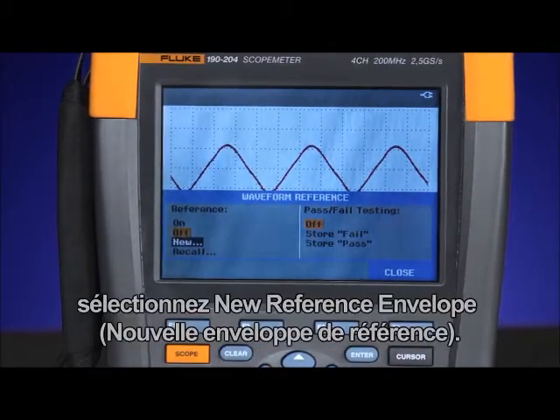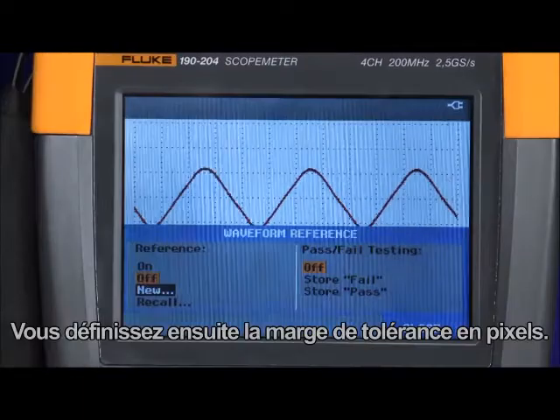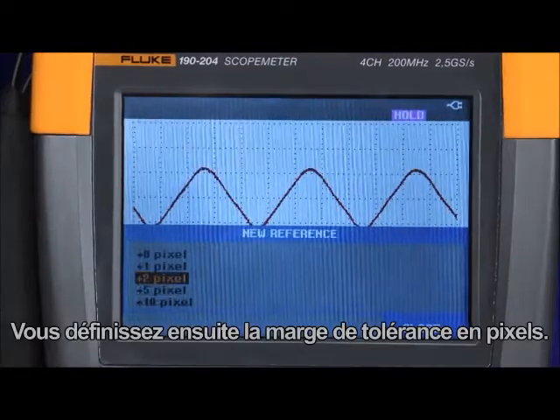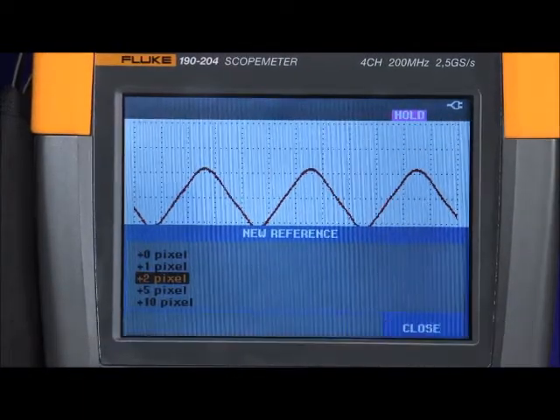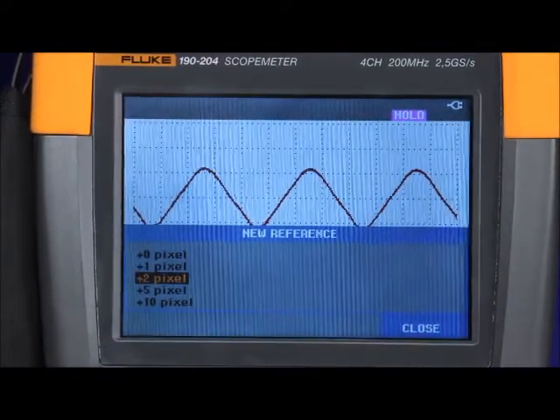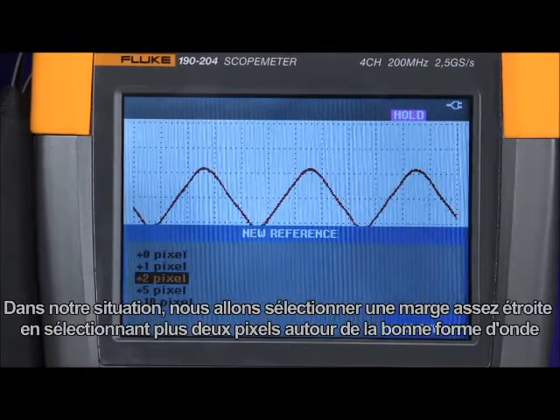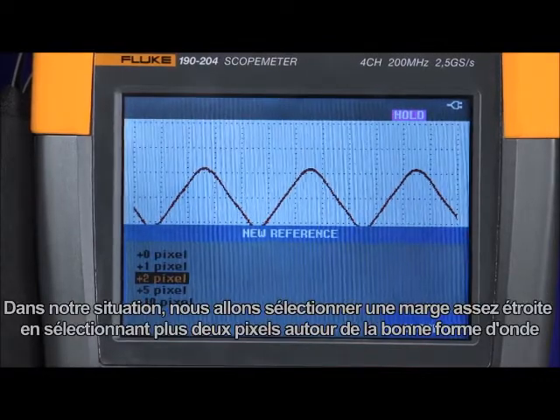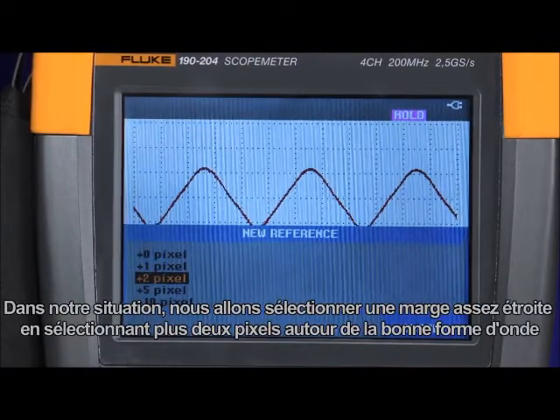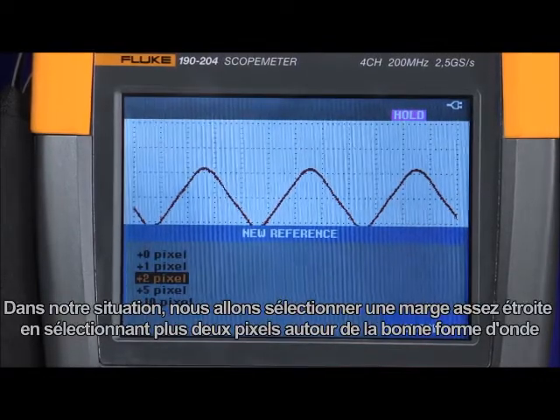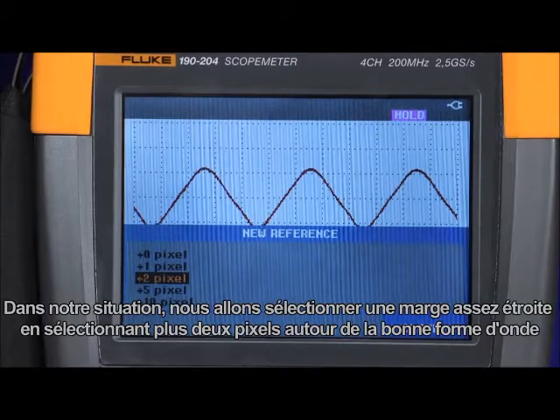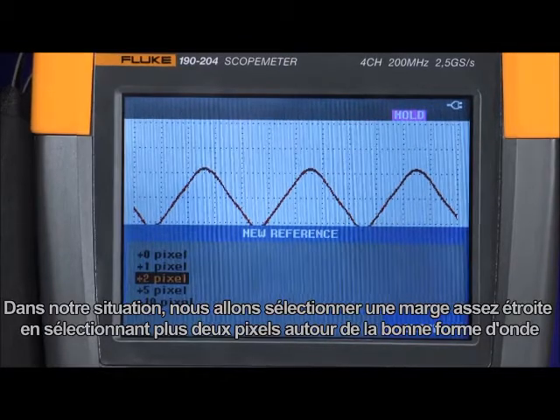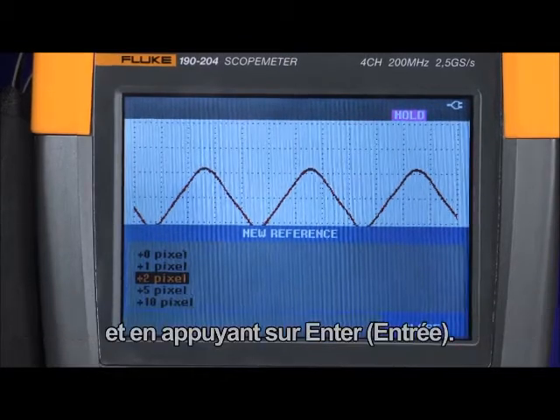In the waveform reference menu, choose a new reference envelope. Here is where you define the window of tolerance by the number of pixels. In this instance, we'll choose a relatively tight window by selecting plus two pixels around the known good waveform, then pressing enter.